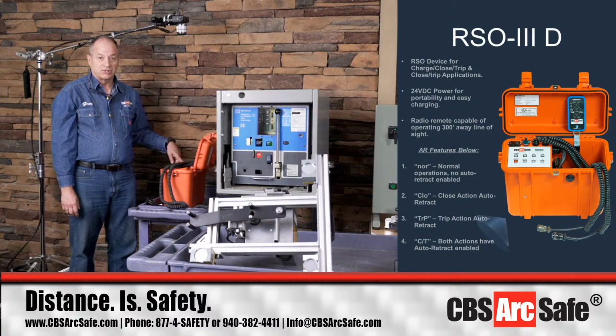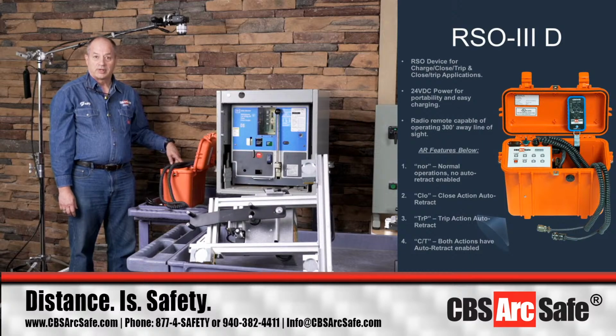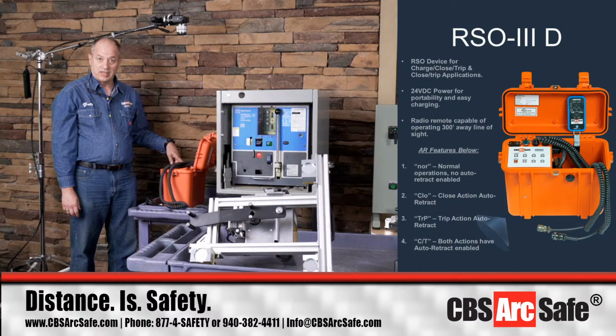But if you've got aging gear and you want to keep your people safe, the actuators we have that do charge, close, and trip can work to help keep your operators safe and out of harm's way, so they're not standing in front of that breaker when it closes unexpectedly.